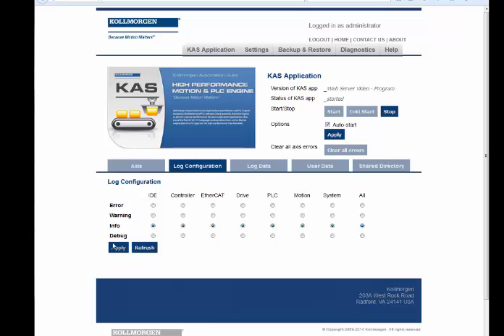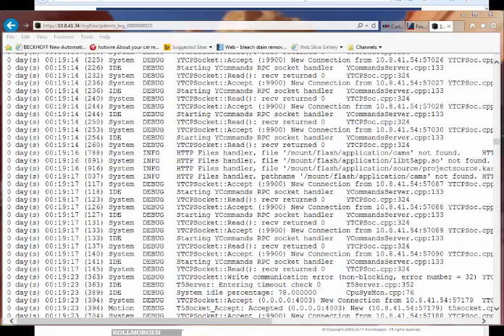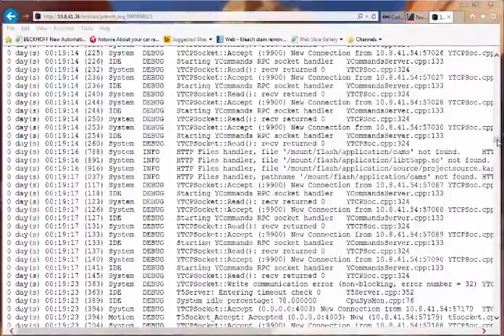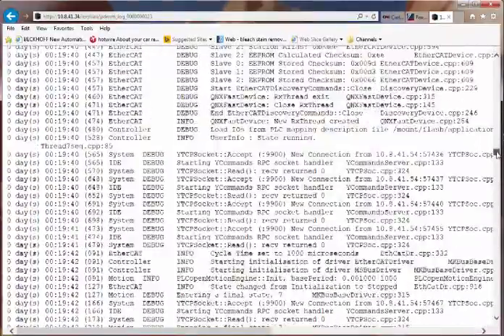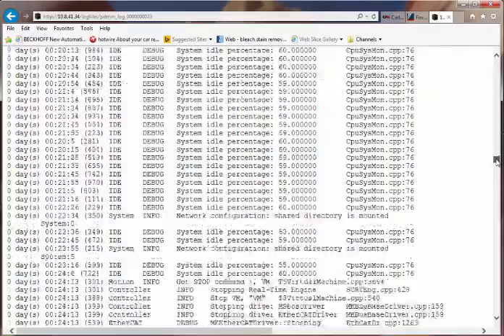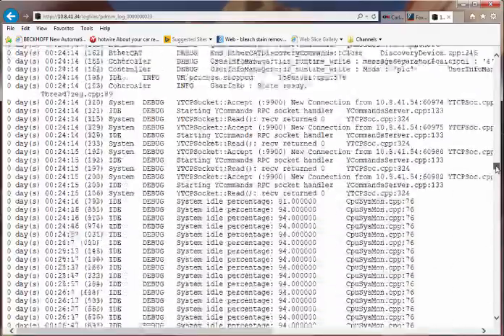In the Log Data tab, the log files can be viewed. These messages can help describe the current state of a system and help identify any operation errors encountered during operation. Log data is collected and updated every 15 seconds. A new file is created when the current file is full. Clicking on the Log will open it up in the browser. Log files are stored in the controller's internal flash memory.